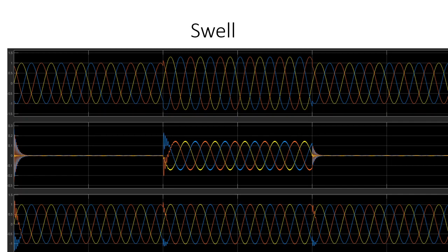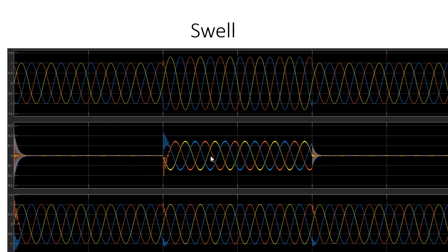This is the output of my voltage swell simulation. Initially, at 0.1 seconds, my system faces a swell — the voltage raises from 1 per unit to 1.25 per unit. My DVR operated at that specific time and absorbed reactive power to compensate for the extra voltage. At 0.2 seconds the swell ended, so the DVR operated for that 0.1-second duration and my voltage was restored back to the nominal values. There is some chattering effect at that point which we'll discuss in the next video.